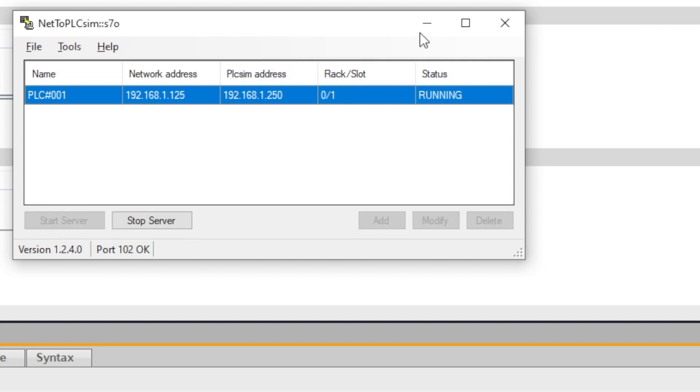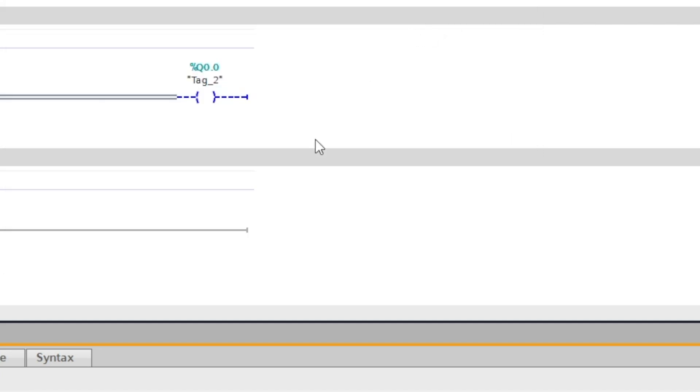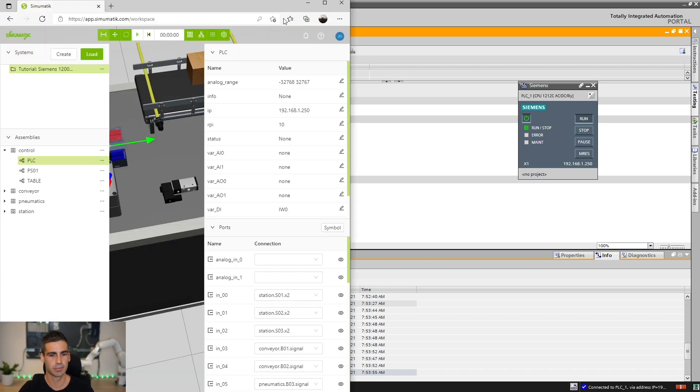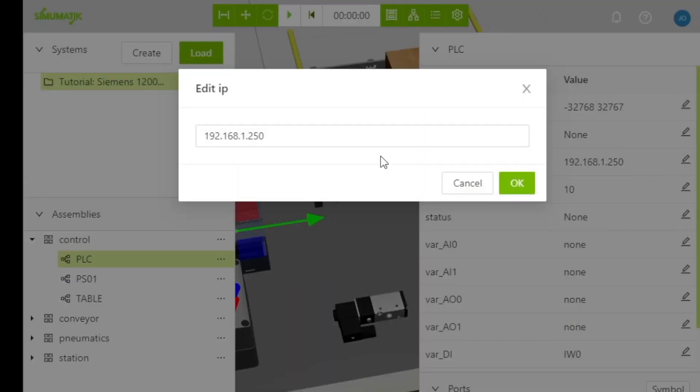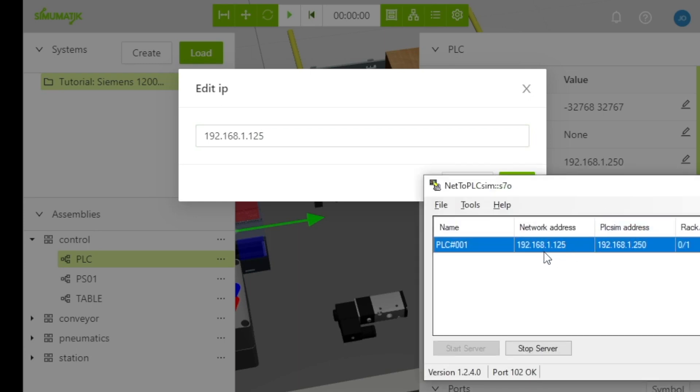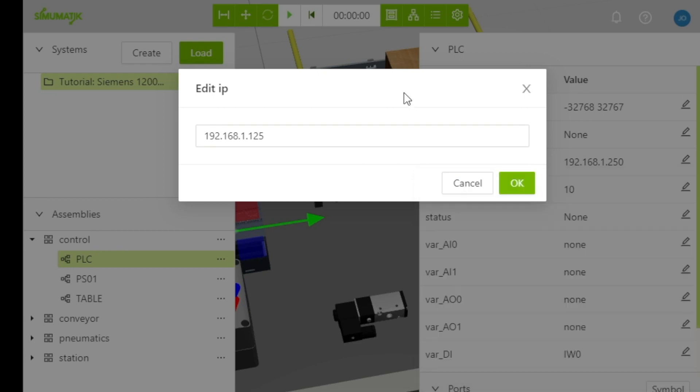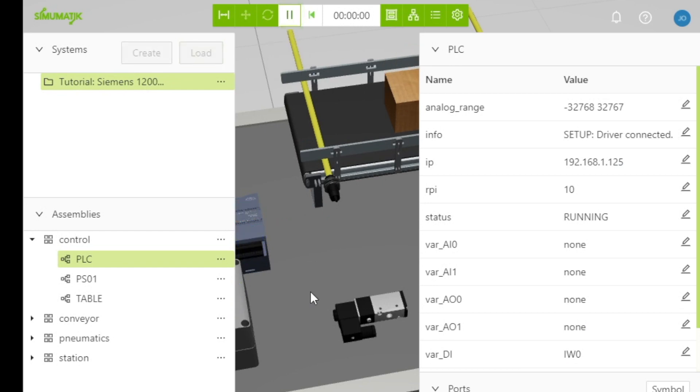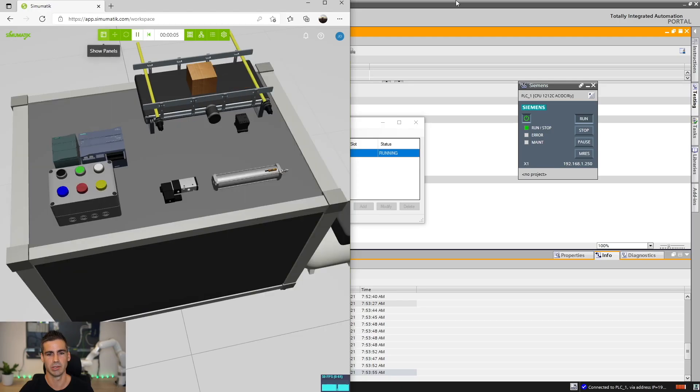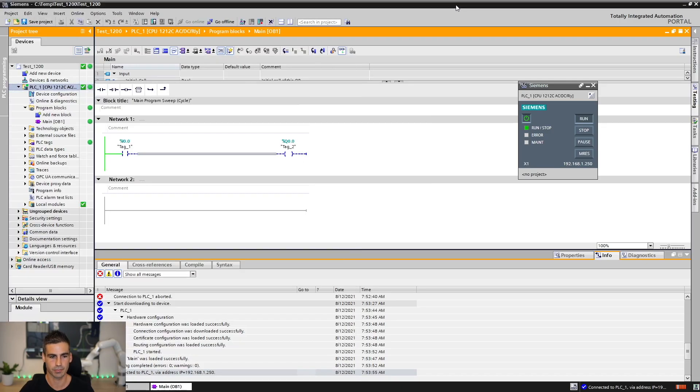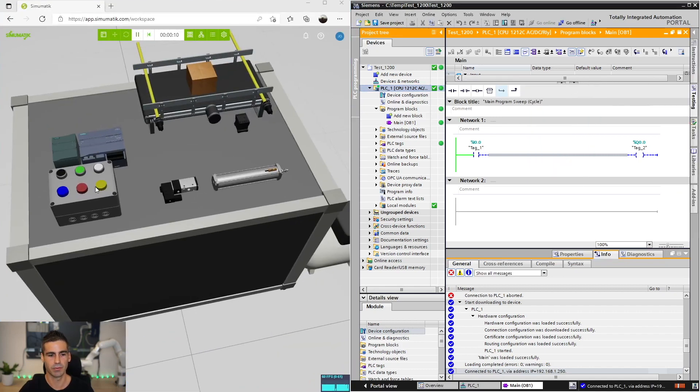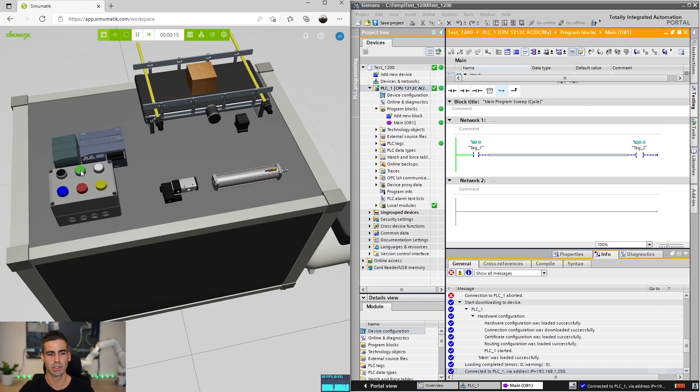Let's start this and now in Simumatik I didn't change anything but we can go here and replace the IP address for 192.168.1.125 which is the one that I have here, the network address for my own computer network address and I just click OK. From here I should be able to click play and now I'm connected - Simumatik is connected to PLC SIM. Let's see what happens here. If I press this button you see now the program is working exactly the same as before but in this case we are running against PLC SIM.